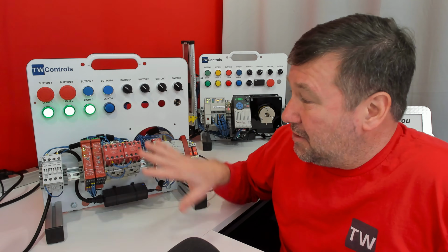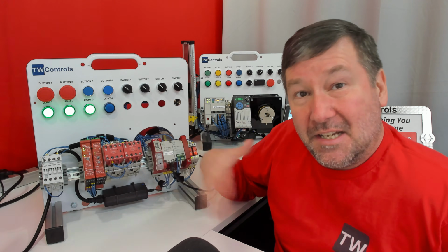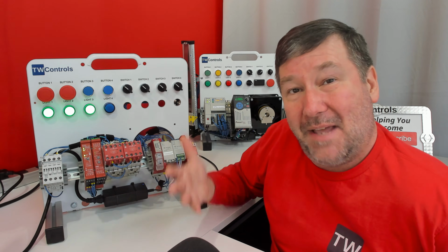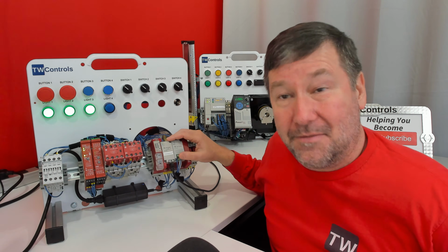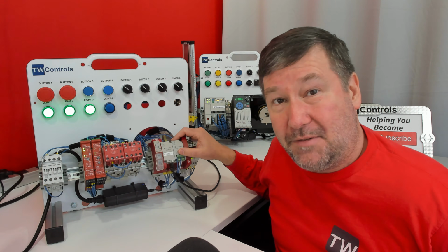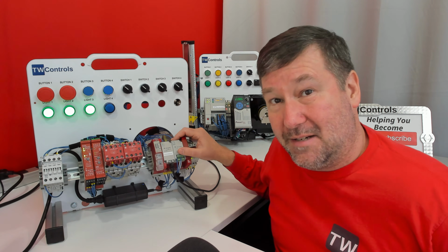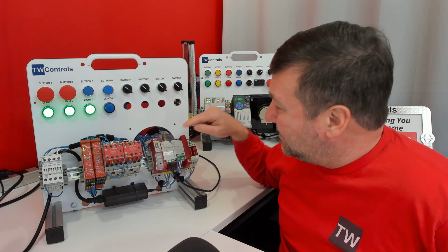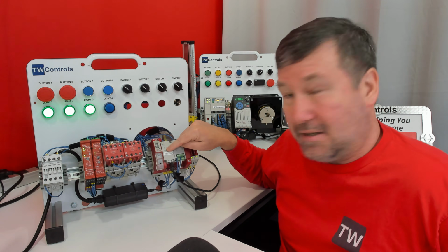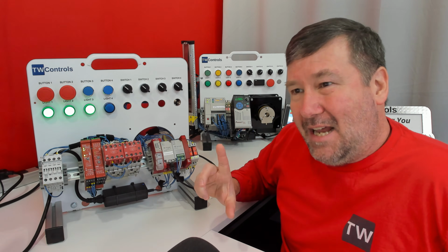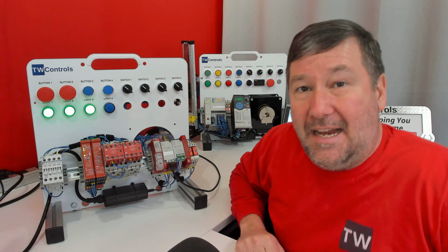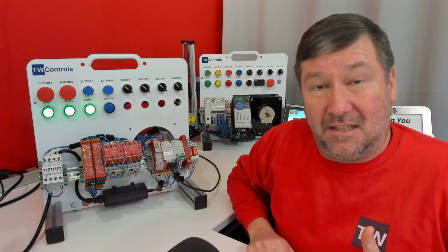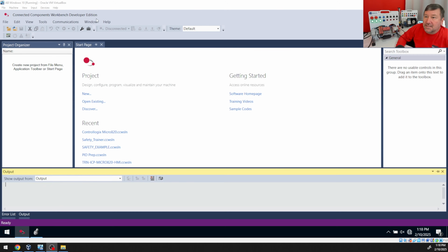We've been going through different types of safety circuits to understand troubleshooting them, and one clear advantage of the CR30 configurable safety relay is that, in addition to it being well configurable, you can get it with the Ethernet option on the front of it. And while we can't really do Ethernet safety with the CR30, we can get a lot of good diagnostics information. So in this video, we're going to diagnose it with Connected Components Workbench.